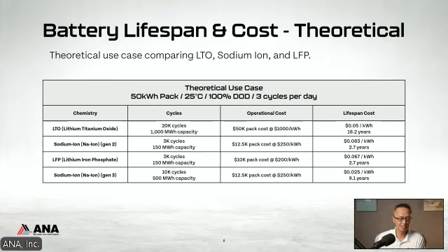Let's look at the three chemistries, LTO, sodium, and LFP. You'll see that LTO has 20,000 cycles at 100% depth of discharge. That means for a 50 kilowatt hour pack, you have basically a gigawatt hour of capacity. Currently the cost is quite high for LTO.